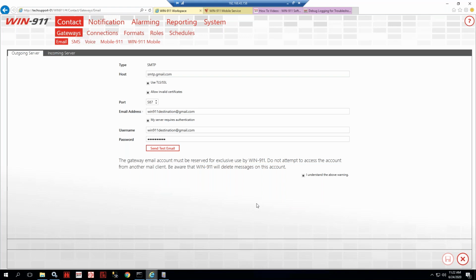You can send an SMS message to a phone by putting in the phone number at vtext.com or whatever the provider's domain is, right? And it'll work today, and then it won't work, and we can't do anything about it because the provider changed something on their end. They changed the domain a lot. They changed their formatting. You can't ACK back through email to SMS transition because the provider changes the format, makes it an attachment instead of plain text.